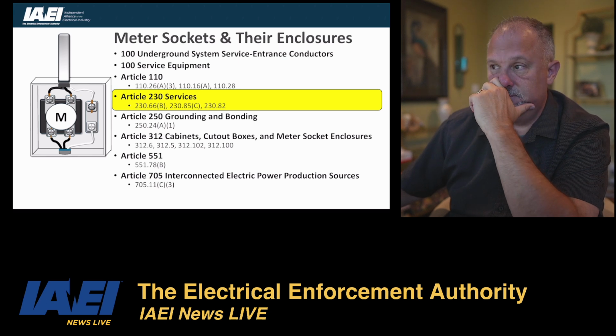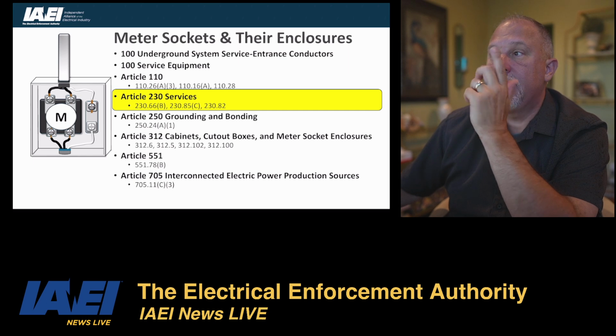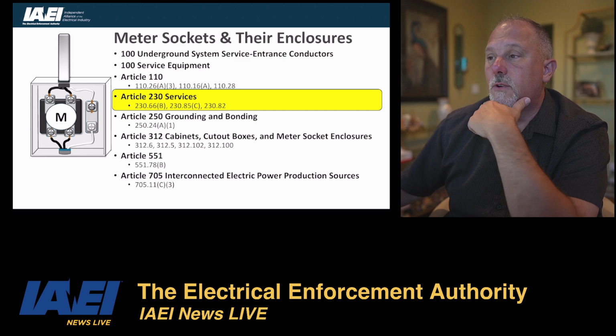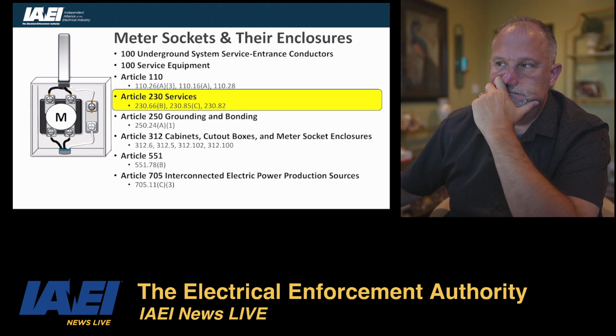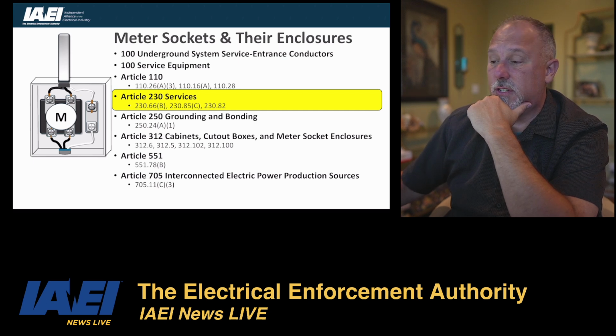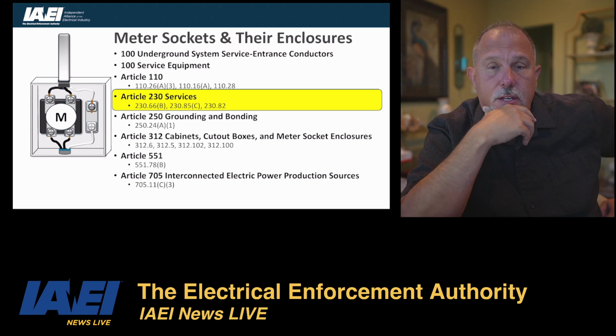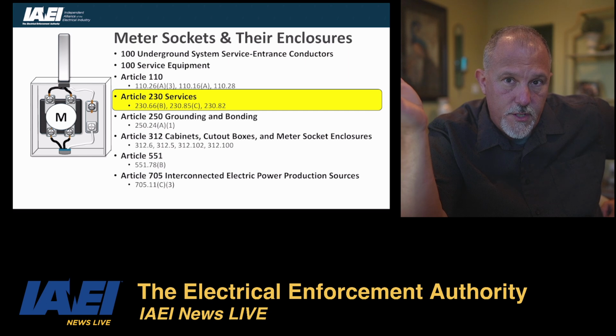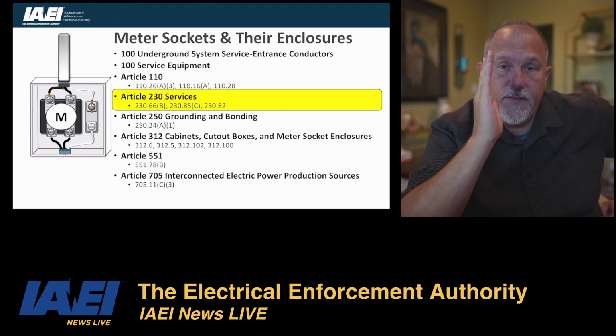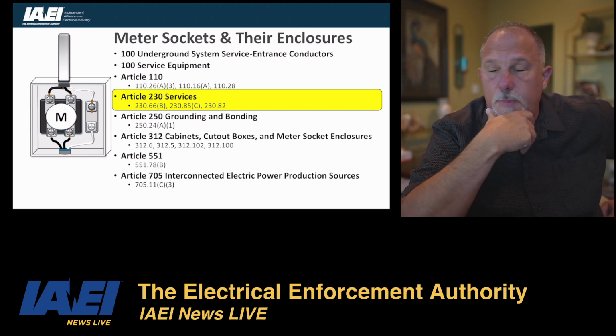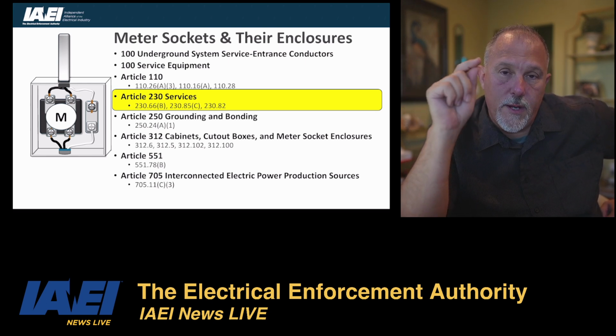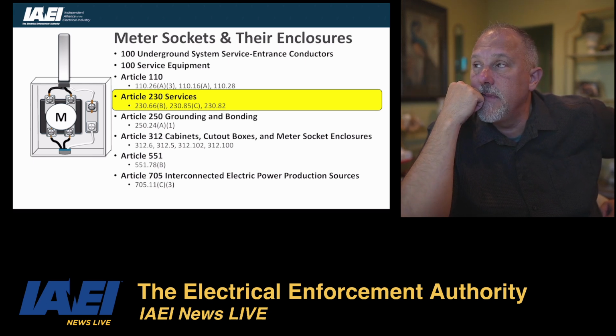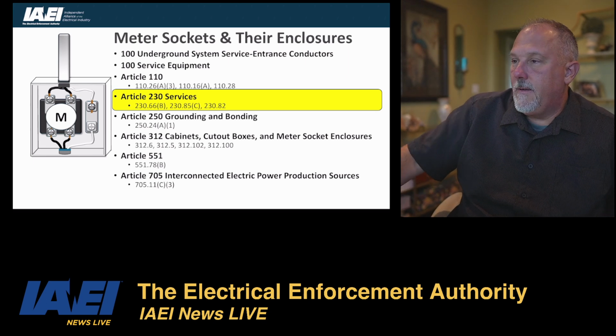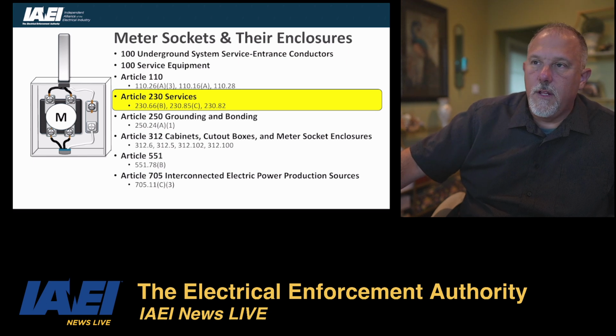It's service equipment. You're going to need working space and the proper depths. That's if it's less than 1,000 volts. If it's greater than 1,000 volts, you're going to a different section. All of that it requires. 110.27, that's your live parts. 110.28, all your enclosure types. So you have to make sure that you're using the right equipment for the application. If it's outdoors, if it's a 3R enclosure, if it's mounted on the wall, you're good. But remember, a 3R enclosure cannot be put on its back. You've got to think about what are the proper NEMA enclosure that you're putting out there for the environment. All right, so 110 is a smorgasbord of a lot of different requirements.